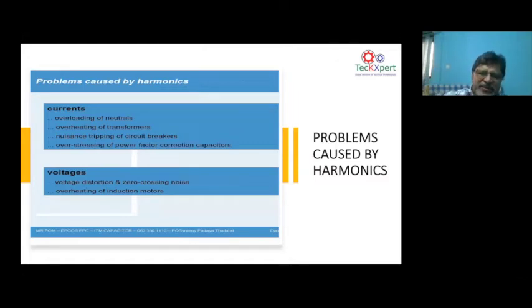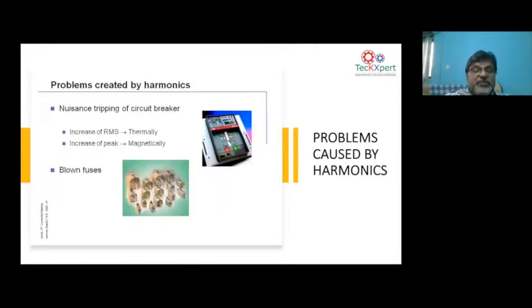This negative sequence current can create a reverse torque on the rotor, and the bearing can fail sometimes. The motor can overheat, the motor can fail. So one of the impacts of overheating of induction motors due to harmonics is because of these negative sequence currents. Go to the next one. Yeah, that is again the fifth harmonic current.